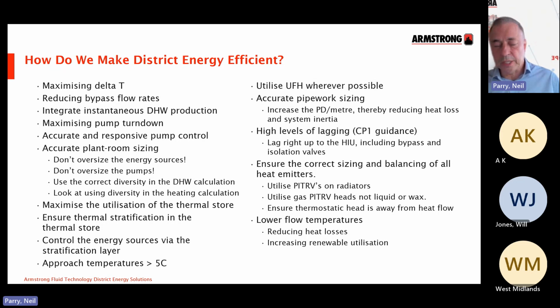And then one of the key aspects with any district network is to work back from the far extremities of the system. So even in those index apartments, you'd start to look at the radiators, the heat emitters, and make sure they're balanced properly. Make sure that pressure independent TRVs are used. Utilize gas heads because they're faster reacting, and then slowly work your way back towards the plant room. If the heat emitters in the apartments are not balanced correctly, you're going to really struggle to hold a good delta T on the system.